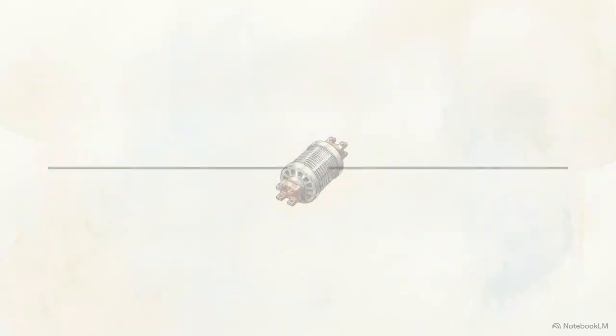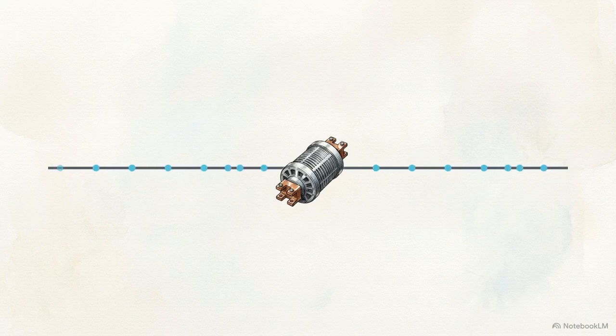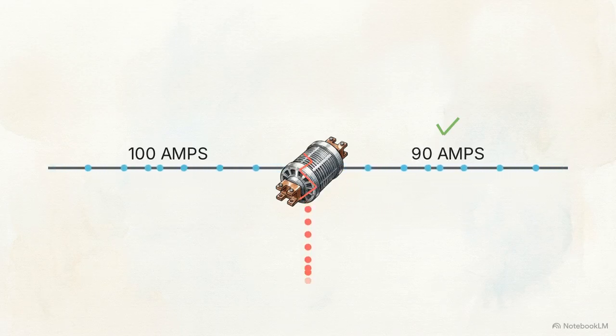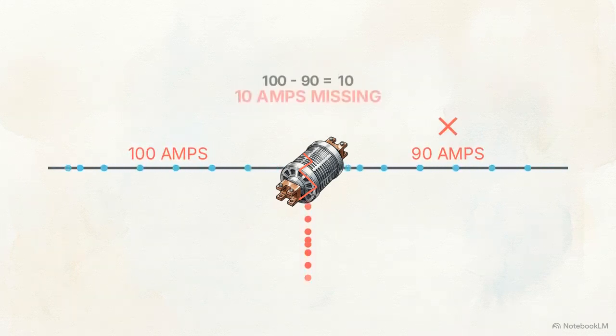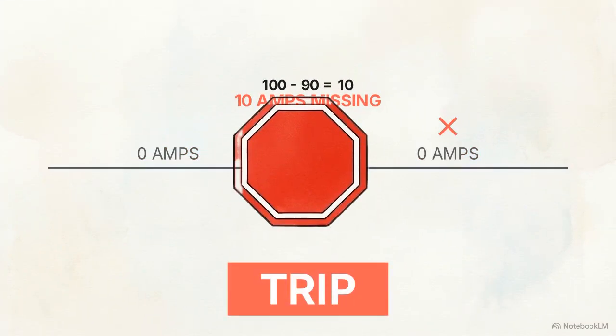Let's look at this animated diagram of a power generator. One way relays watch the math is through percentage differential protection. The logic follows strict conservation. If 100 amps of current flow into the machine, exactly 100 amps must flow out. If the insulation inside the generator breaks and electricity starts leaking into the metal frame, only 90 amps might exit. The relay sees that 10 amps are missing. The math no longer balances, so the relay immediately fires a trip signal to shut the system down.